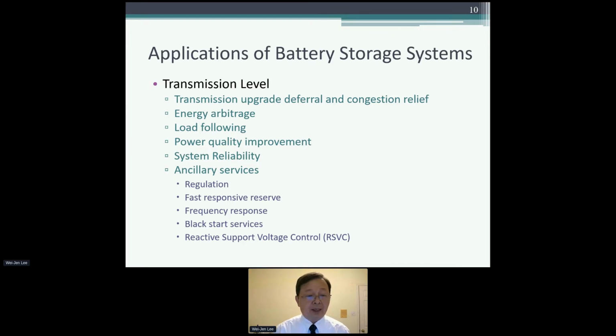If you look at some of the units, we always have to prepare for system blackout, and some generation units will be tagged as a black start unit. With the battery storage system, they can provide this kind of service. I've seen some power plants, because they try to do the black start, have to either install the diesel generator inside the plant or put the battery storage inside the plant. At that time, the battery storage basically sat on the shelf waiting for the outage.